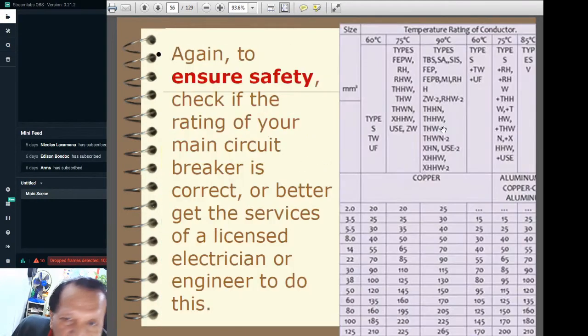Okay, here is a reference for the kind of wire. These columns indicate the ampere capacity for each size of wire. Like here, 2.0 mm wire, 25 amps for a THHN or THHW, and so on. A 3.5 mm, a bigger wire, would allow 30 amps. 5.5 mm wire would allow 40 amps only. 8.0 mm wire should allow up to 50 amperes. Okay, and 14 mm, 55 amps. 22 mm, 70 amperes, and so on and so forth. So you have to be very knowledgeable in the selection of wires and, of course, the protection.